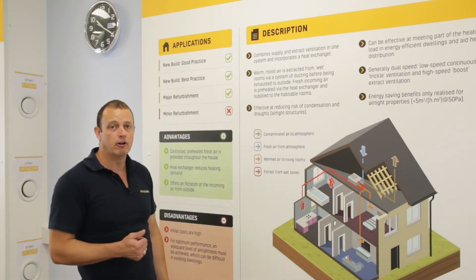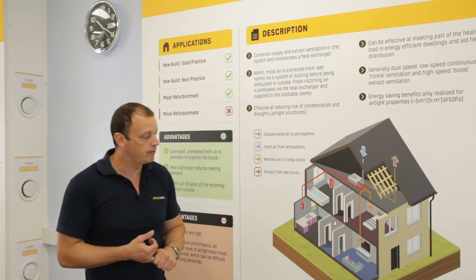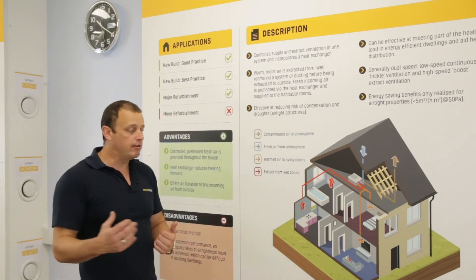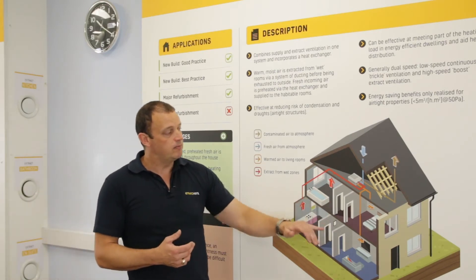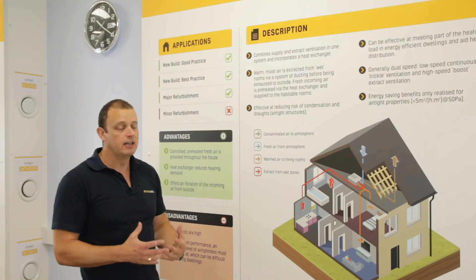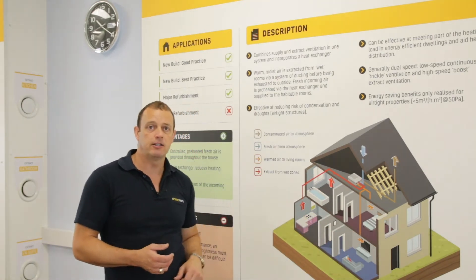Your heating system's not going to have to work as hard to warm that air up. Whereas with System 1 and System 3, you're taking air out at 20 degrees and bringing unfiltered, untempered air in from outside, so your heating has to work a lot harder. With a heat recovery system, you're bringing air in tempered to maybe 18 degrees - your heating system only has to heat it up another 2 degrees to get it back to 20 degrees.